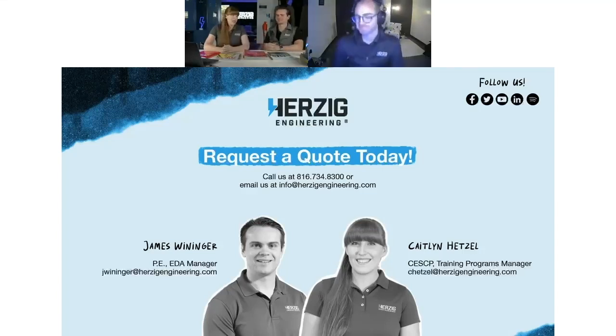The MTS is just available for purchase. This is not required, but recommended that you refer to it for maintenance, testing, specifications, as well as circumstances in which you should update your system studies that are in the 70B, which is any time there's a change that could affect the results, not just every 5 years.